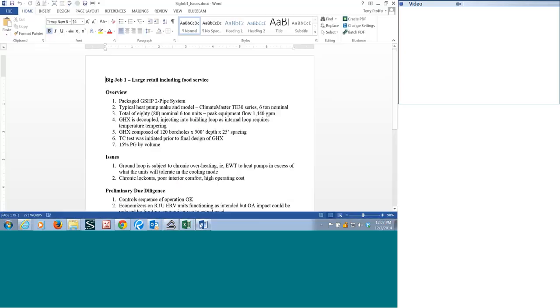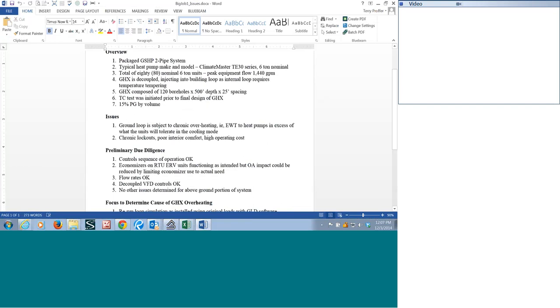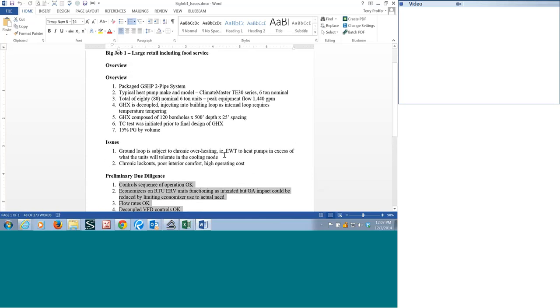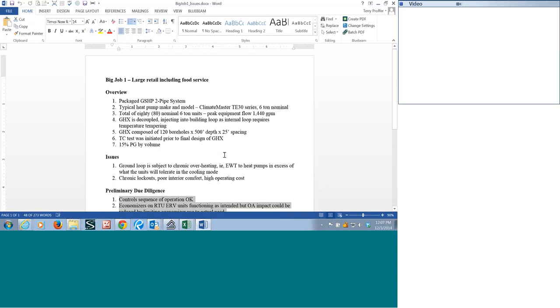That's good. Okay. What I'm going to do first is give you a little bit of an overview. I've done kind of a composite system based on some other projects we've done that had the issues we're going to describe. One of the things that's critical on evaluation, as we covered in the last seminar in November, was preliminary due diligence to make sure all of your above ground portion of the problematic system is not the problem. So with that, we're going to make an assumption that for the most part, everything above ground, the heat pumps are correct, the sequence of operation controls are correct, we don't have conflicts with too much outside air, that sort of thing. So we're going to assume that we have a package 2-pipe heat pump system.